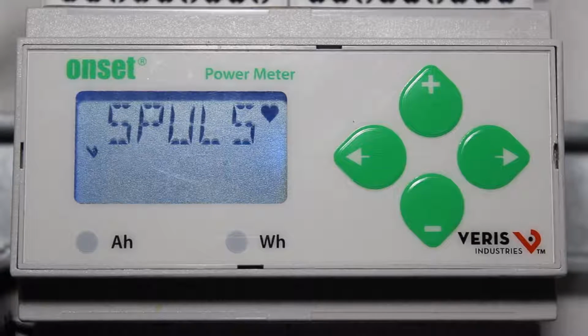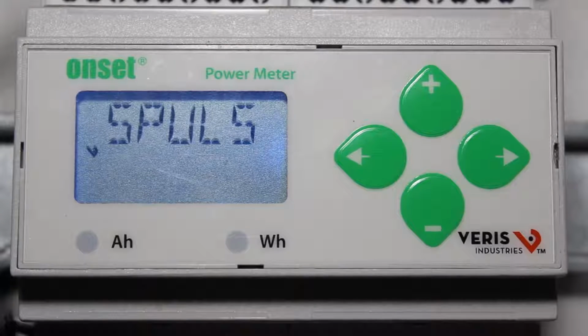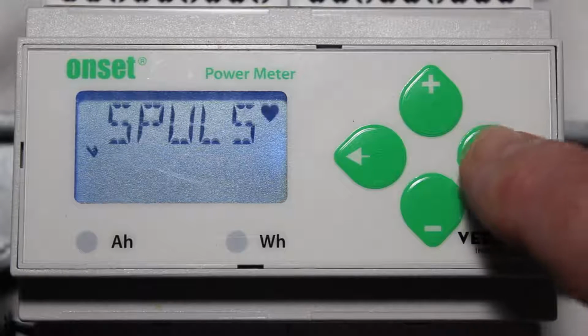Probably the most important set of parameters we want to set are the S-pulse. S-pulse is giving a pulse weight to the actual pulses that are coming out. So we're getting pulses that are watt hours, amp hours, and VAR hours. And that's what we're logging with our HOBO data logger, and we're going to post-process that data. Either HOBOware is going to do it for us, or we have to do it in a spreadsheet if we're using something like a UX120 or an energy logger or the RX3000. So it's important to get these pulse weights correct based on your application, and there's a lookup table in the manual. This is very handy, and it's color-coded, so it's very easy to follow, but you want to make sure you put in the right pulse weights for the number of phases you're monitoring and the size CT and voltage range. So we want to get into S-pulse, right click.